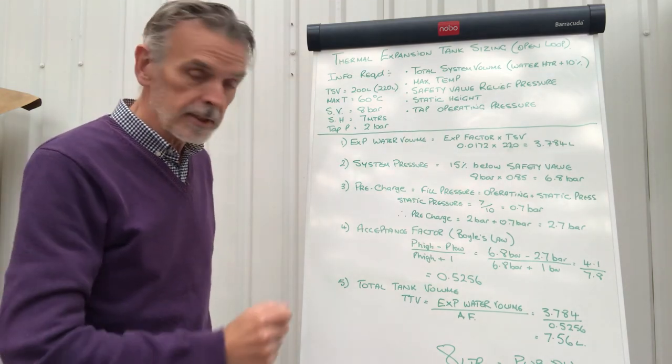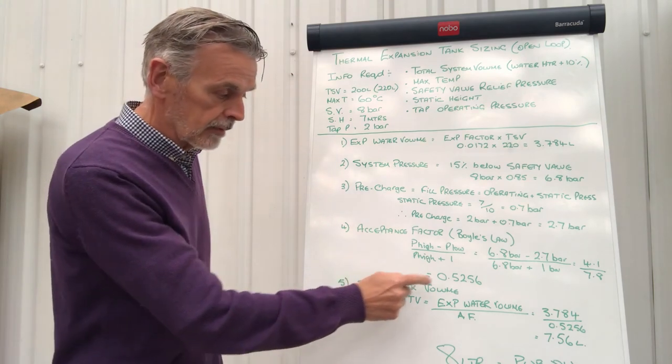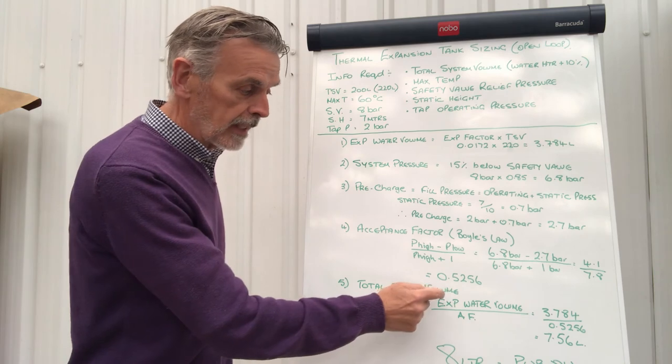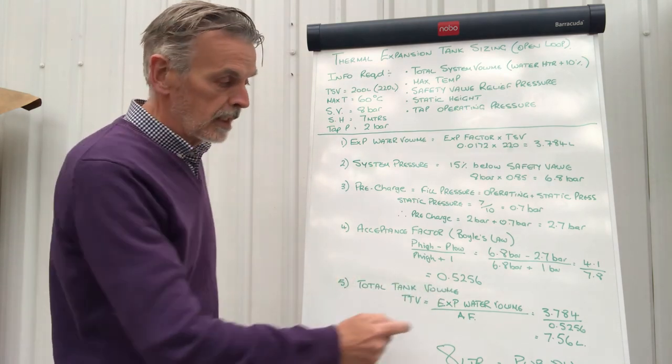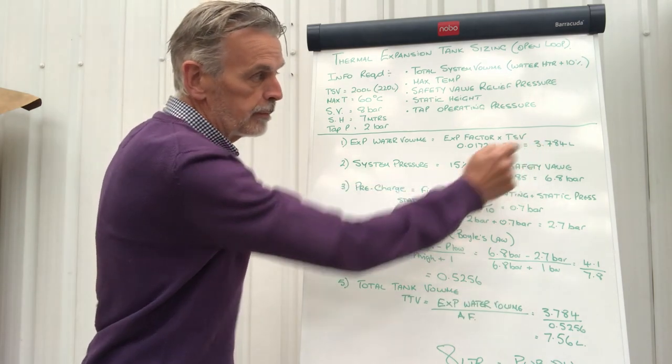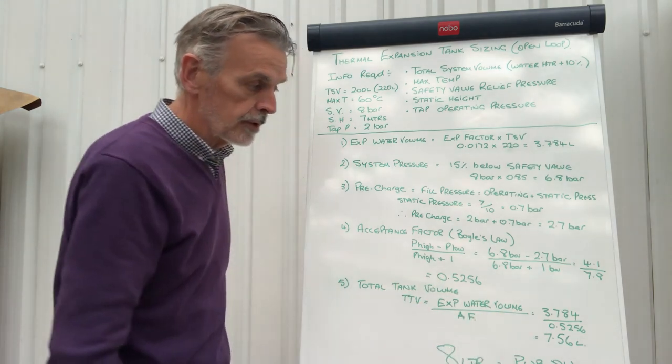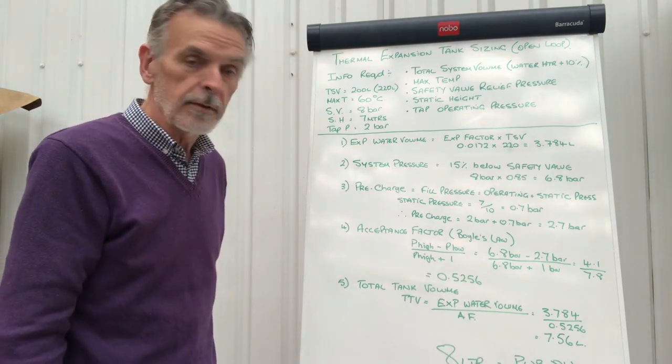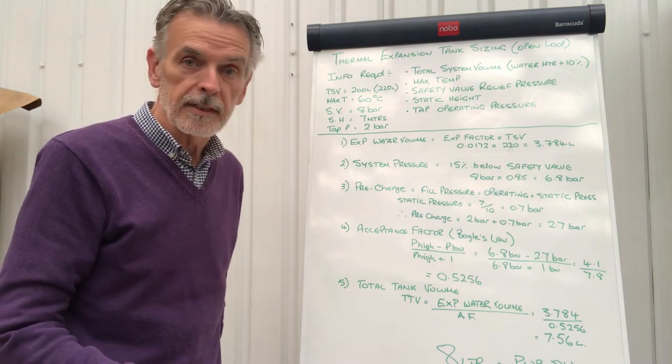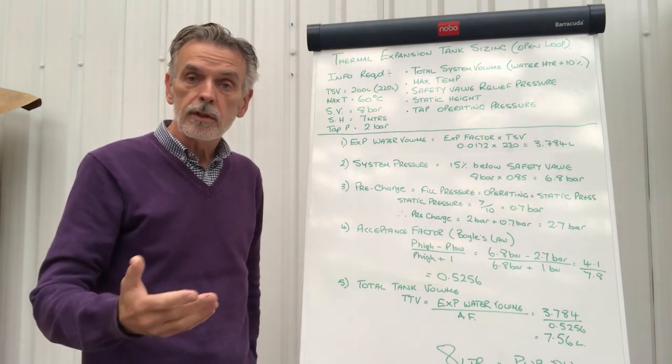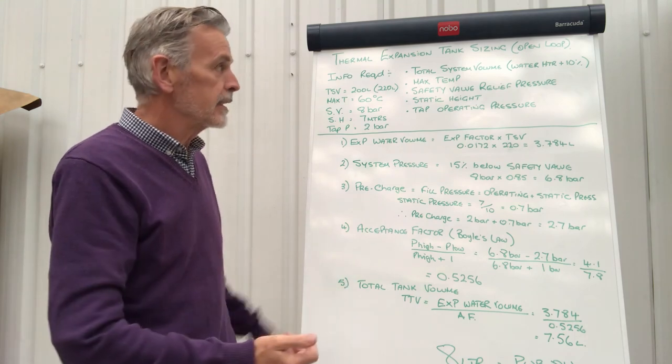Final calculation now to get your final tank size. And the total tank volume is the expanded water volume divided by the acceptance factor. And the expanded water volume of 3.784 divided by the acceptance factor of 0.5256 gives you a tank size, total tank volume, of 7.56 litres. We would always go, you should always go one size higher than that, so that would be an 8 litre tank.